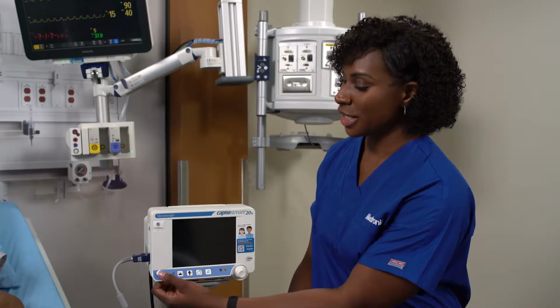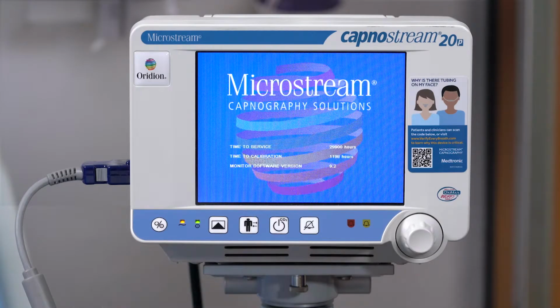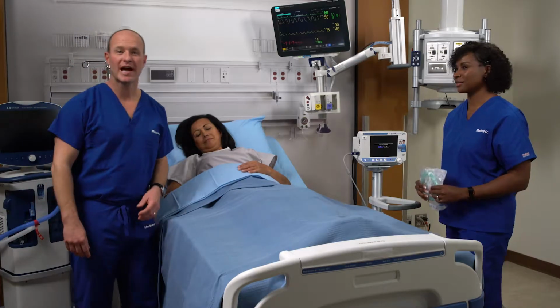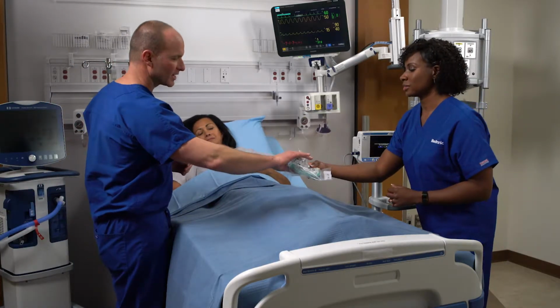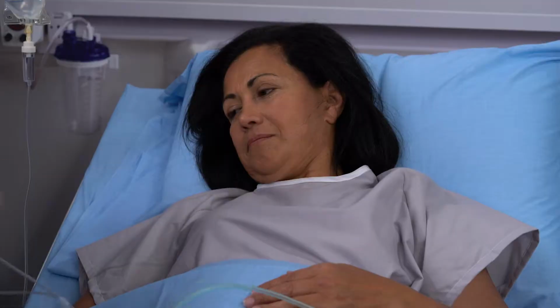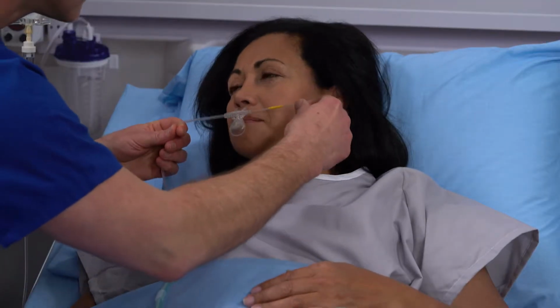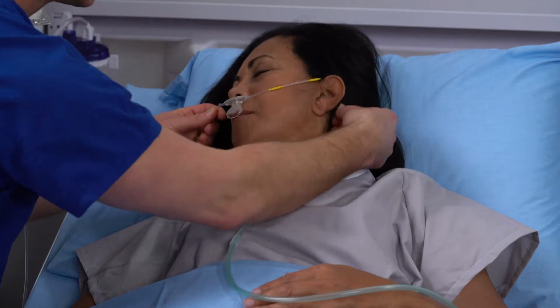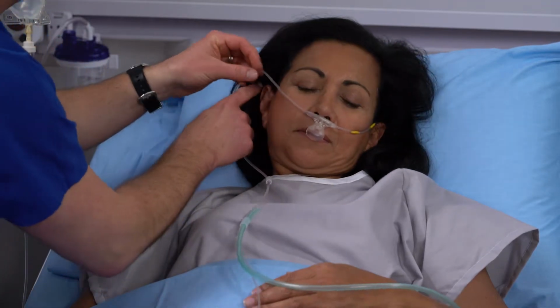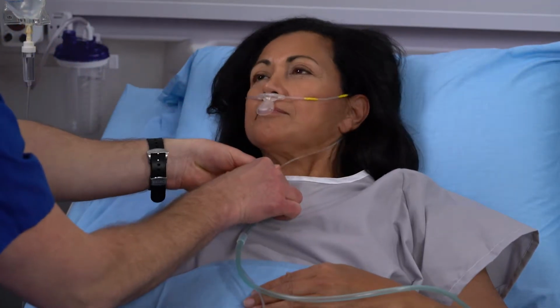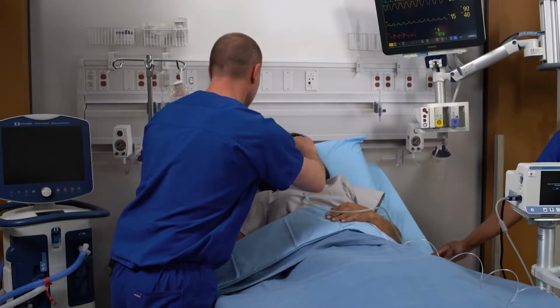The power button is here. Simply turn it on and you're ready to go. There's no need for calibration. Let's look at how to attach the appropriate filter line sampling line to the patient. The sampling line has a built-in hydrophobic filter and quick seal connector, and it samples exhaled CO2 from both the nose and mouth.